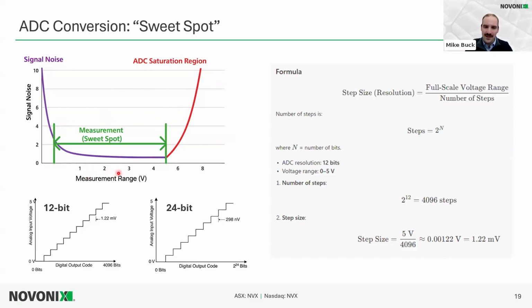So there's a formula I want to go through. In this example, we're using a 12-bit ADC with a voltage window of 0 to 5 volts. 12 bits is the resolution, meaning there are 4,096 steps, or 2 to the power of 12. Converting that to a measurement resolution, as discussed earlier, gives a 1.22 millivolt resolution. That means the minimum detectable step change the ADC can handle is 1.22 millivolts.